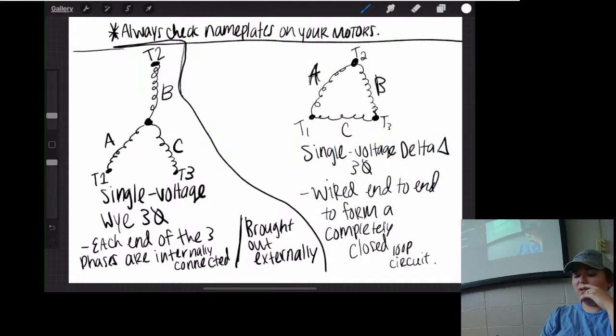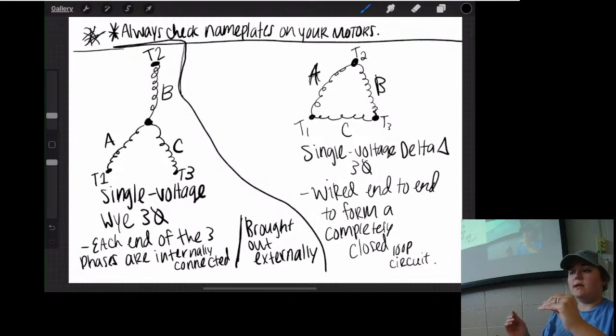Now let's throw this out there - it's very important: any information you need to know about a motor should be on the nameplate. So if you need to know what temperature this motor can resist, or what is the rated speed of this - in this limited amount of time, what should this motor be producing? And if it's not, there's a problem with your motor. That's how you troubleshoot. The first thing I would do is look at my nameplate if I'm troubleshooting something - what could have happened, and was it operating within its capacity to operate? You get what I'm saying? So I just threw that out there - nameplates are very important.